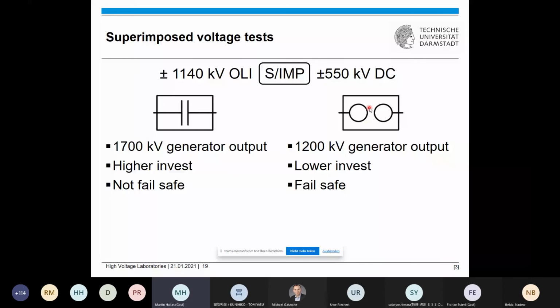And here are three arguments which were for us the major arguments for our decision. Well, for a coupling capacitor, you will need a higher generator output because you have to overcome the DC voltage for bipolar testing. So you will need approximately 1700 kV generator output, while you still only need 1200 kV generator output for the spark gap. This is also an argument when you design a new HVDC lab. So a coupling capacitor is a higher investment compared to a very low investment spark gap.